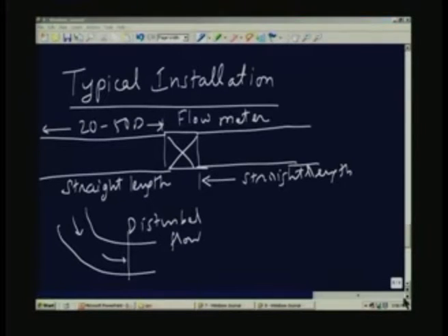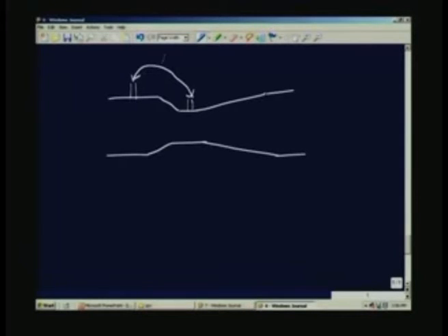The other point I would like to talk about is what is done normally. If you take the venturi for example, this is typically the venturi. So, you are going to measure the pressure difference between these 2 points. This is delta P what I am going to measure. So, normally what is done is, you have several taps on the periphery. So, you have the pipe here, this is the pipe thickness, I have several taps.